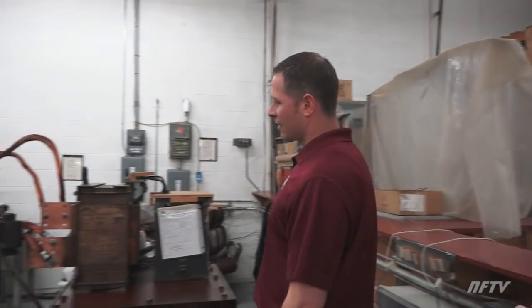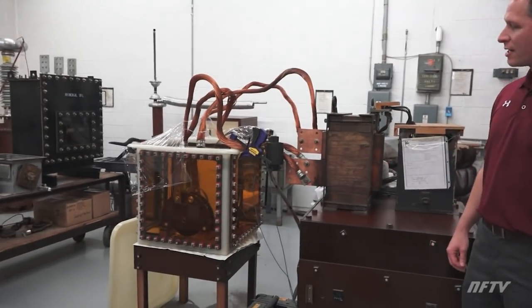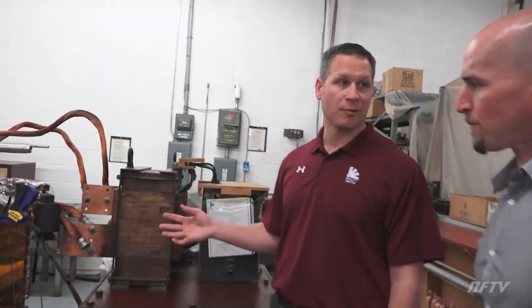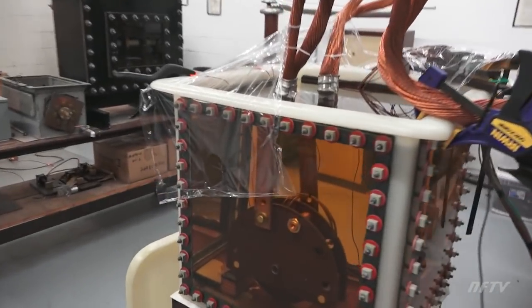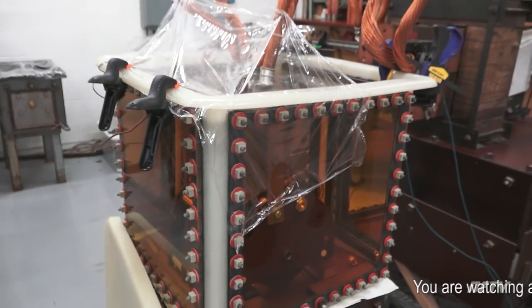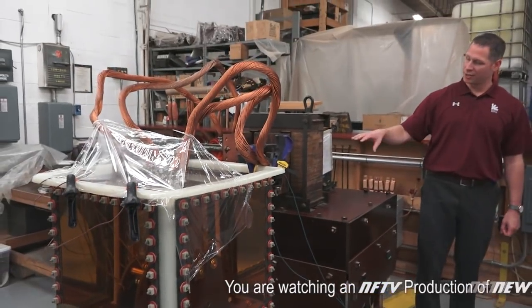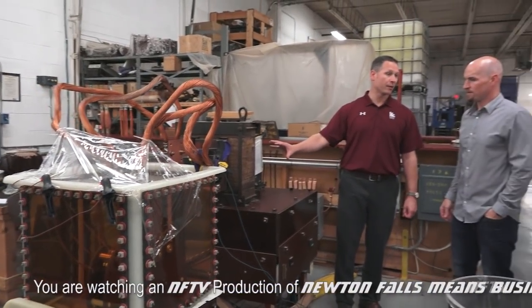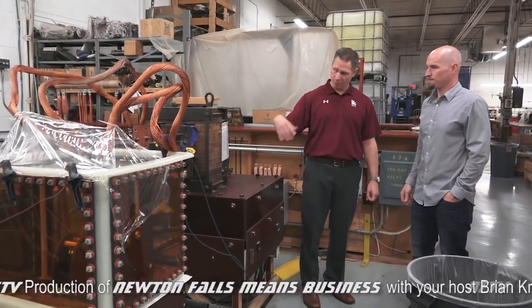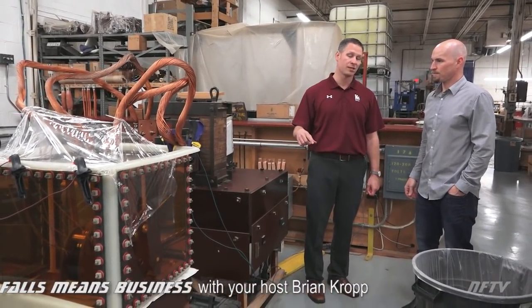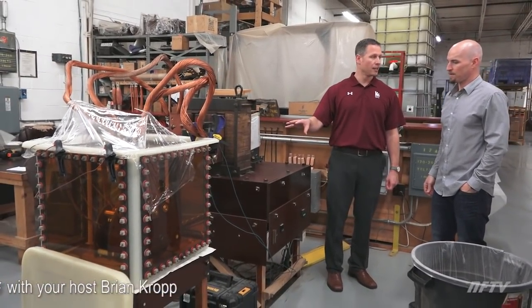This is actually our test area, what used to be our old high voltage test area. We've converted it, but we still do some testing in here, like on some of our switch designs where we put high current through the switch and monitor the temperature. We have one set up here with temperature probes on the contacts, and using this current transformer we can put up to 3,500 amps through a switch application continuously and monitor the temperature rise.